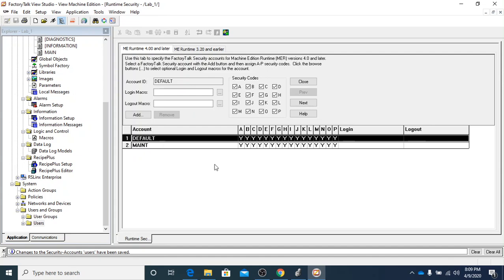But if I have a screen that I want protected, it's going to go under this one. Let's say that for the default, letter A cannot be accessed unless you're in the main screen. These check boxes are the same thing as these yeses — I've got that one unchecked, but there's still a Y underneath the A in default. The accept button came up, so if we click that, now it updates: it's unchecked and it's got a no in there. So now anybody that is logged in under the default and has the letter A designated on the screen, they do not have access to that screen.